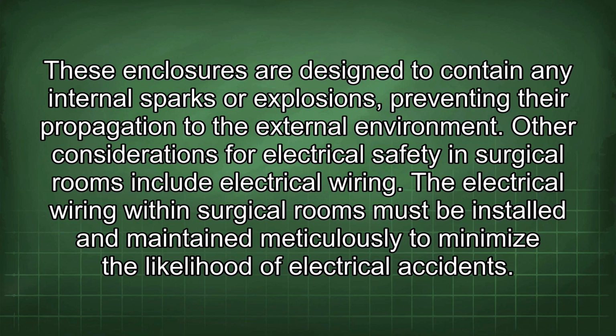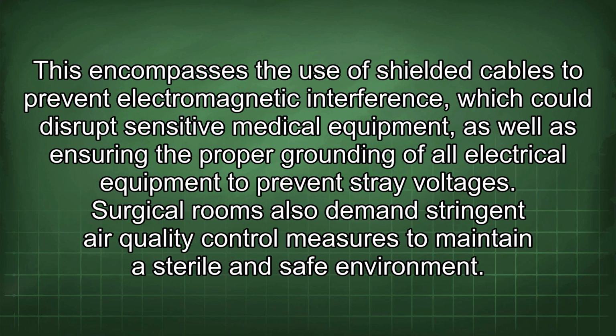Other considerations for electrical safety in surgical rooms include electrical wiring. The electrical wiring within surgical rooms must be installed and maintained meticulously to minimize the likelihood of electrical accidents. This encompasses the use of shielded cables to prevent electromagnetic interference, which could disrupt sensitive medical equipment, as well as ensuring the proper grounding of all electrical equipment to prevent stray voltages.